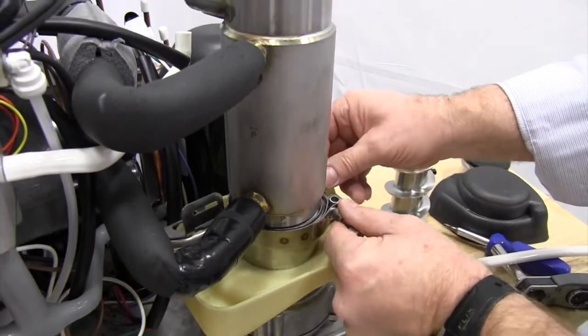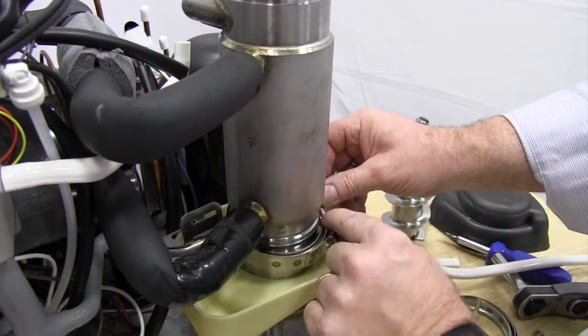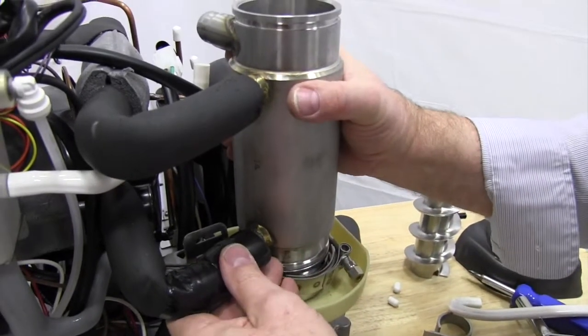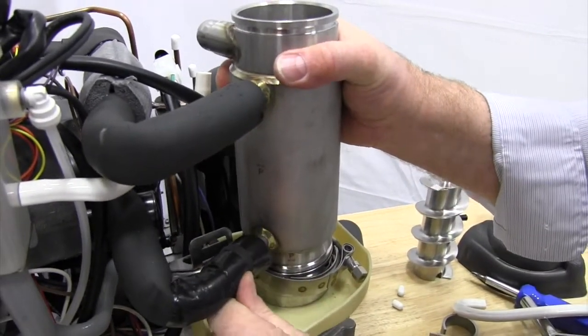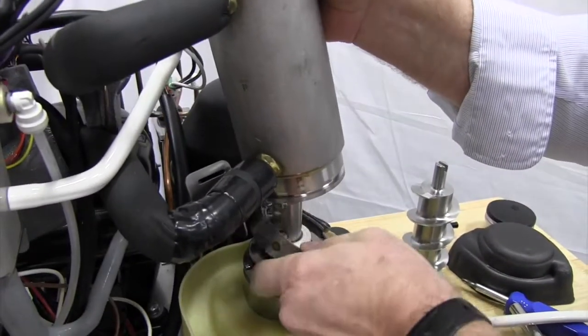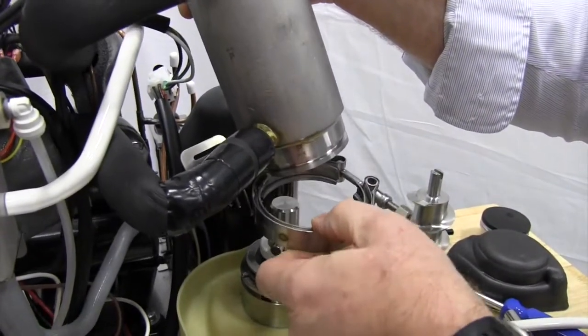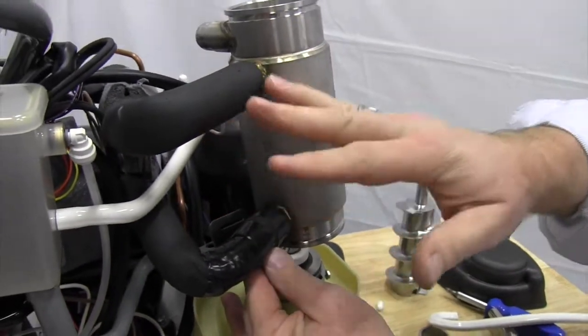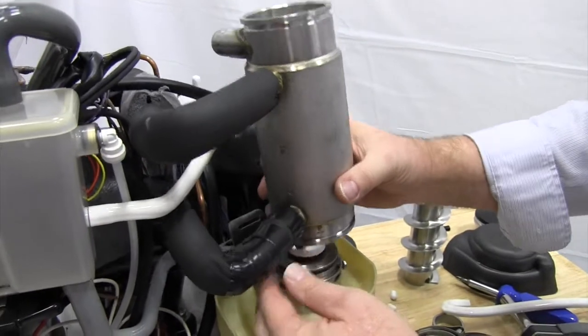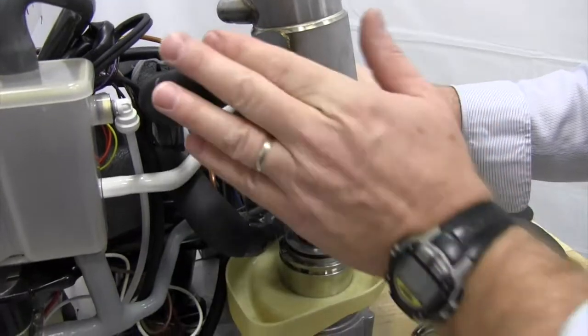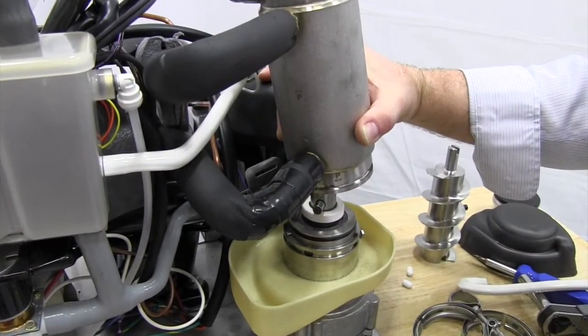I've loosened up the V-band clamp on the lower side of our evaporator. We can rock the evaporator back and forth a little bit and lift that off of the lower bearing. Our refrigerant lines are designed so that there's enough flex in those so you can easily pull this off to get at the lower bearing without having to worry about damaging the refrigerant lines.